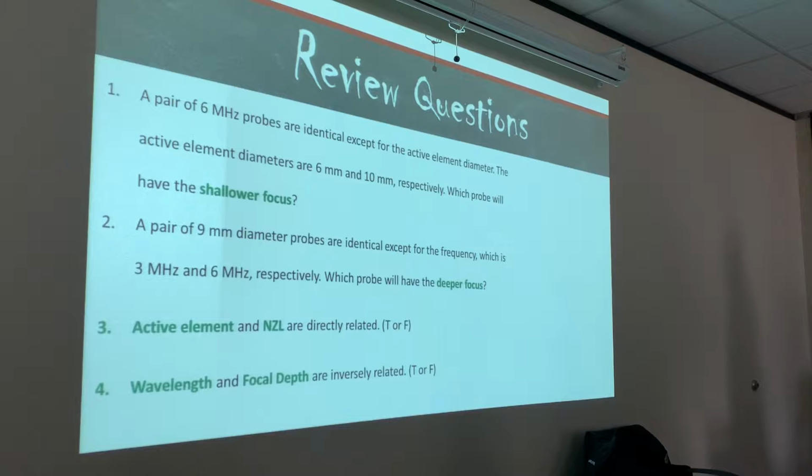Which one of these, a 6 millimeter or 10 millimeter active element, is going to provide us with the shallower focus? The 6 millimeter transducer, right? Because they're directly related. So of course we're going to look for the smallest one because that's going to produce the shallowest focus.